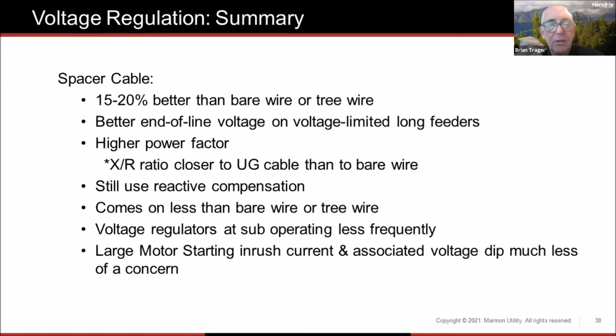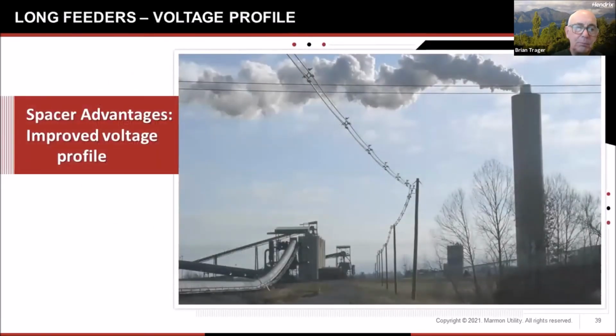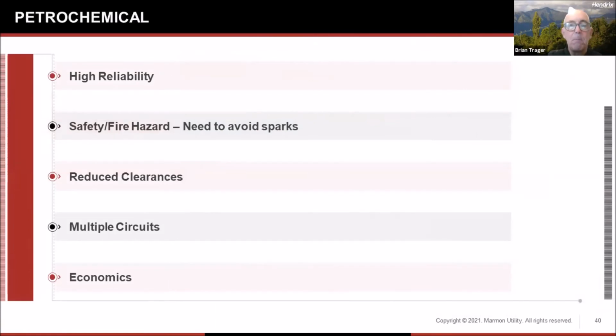And very important in mining and processing facilities is that we have large motors starting inrush current that creates a significant voltage dip. So that's going to be much less of a concern when we're using spacer cable. We don't want to trip those motors offline with the voltage dip. And here, again, we're talking about long feeders. We're worried about the voltage profile. Crushers may be tripping offline with current inrush and voltage dip. So that's one application there.